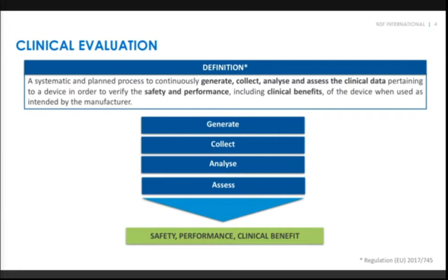Now I would like to start with the content part. So before going deeply into the clinical investigation part, I would like to give you an overview about the current requirements regarding clinical data in general. Each medical device from class 1 to 3 needs to be evaluated regarding the clinical safety, performance, and clinical benefit. A clinical evaluation serves as evidence and is a systematic and planned process to continuously generate, collect, analyze, and assess clinical data. So clinical data could be sourced from 3 different data types.